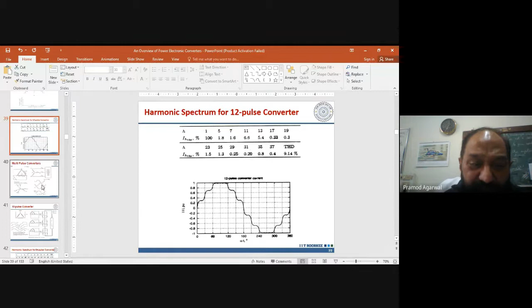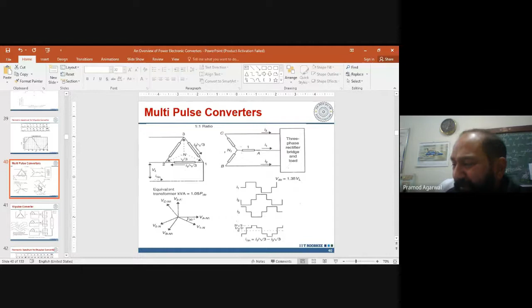You can go for higher pulse also, like 18 pulse, 24 pulse, but there you need a special type of transformer where the phase shift is different. In star delta, we naturally get a 30-degree phase shift, but if we want a phase shift of 20-degree or 15-degree, then we cannot get it from star delta.